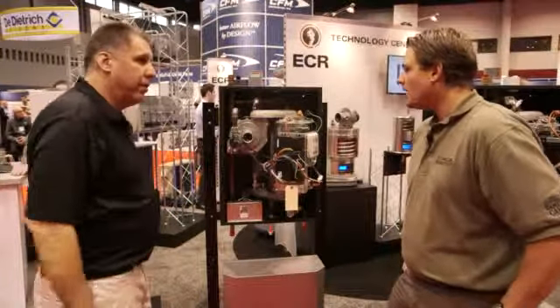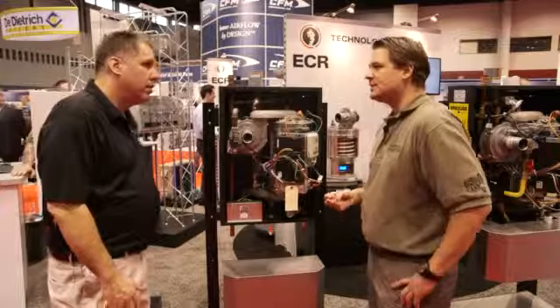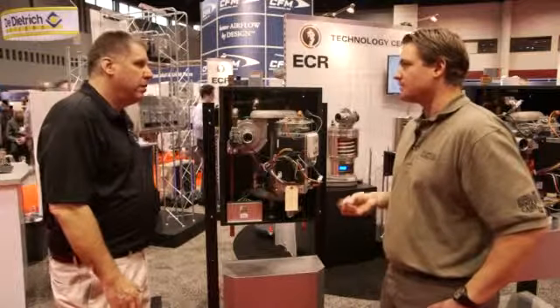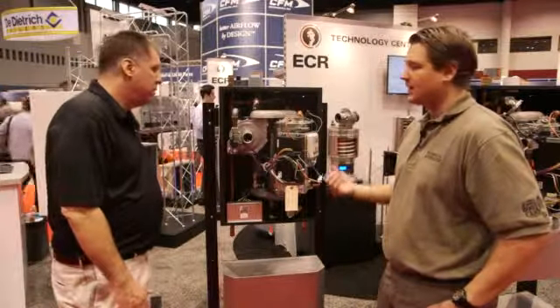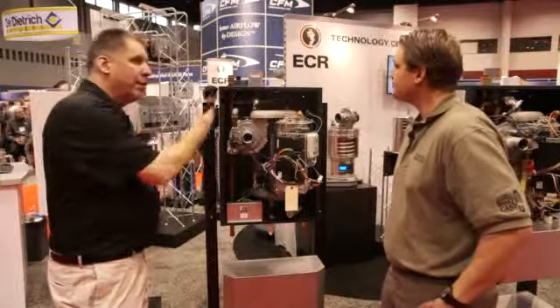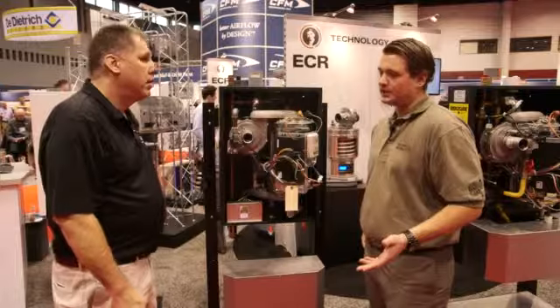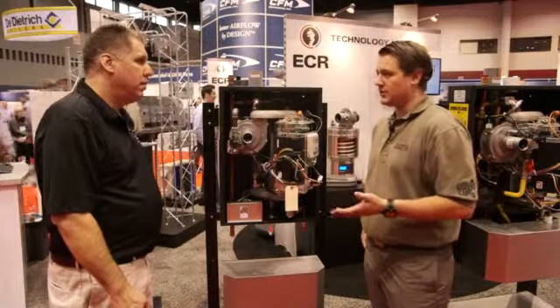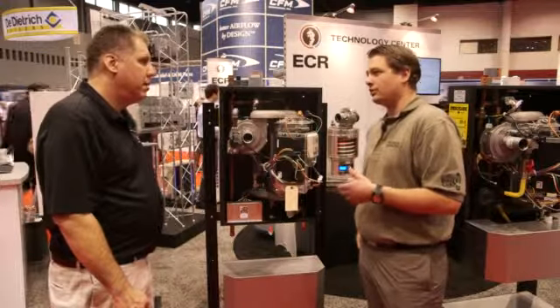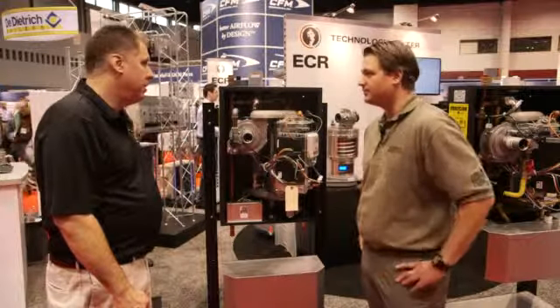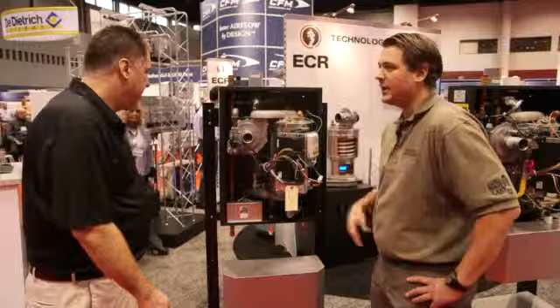Now how about venting? How are we going to vent this boiler? This boiler can be vented in CPVC, PVC, or polypropylene. So it still uses the same venting parameters as our SSC would. And Simon, how far can I go with that vent pipe? For 50,000 BTU, you can go 100 feet in 2-inch. For the 75 and the 100, you're at 50 feet for the 2-inch. If you want to go longer than that, you can go to the 3-inch pipe and you get 100 feet out of it. So you can go a good distance with this. You get 100 feet out of all of them, yeah.